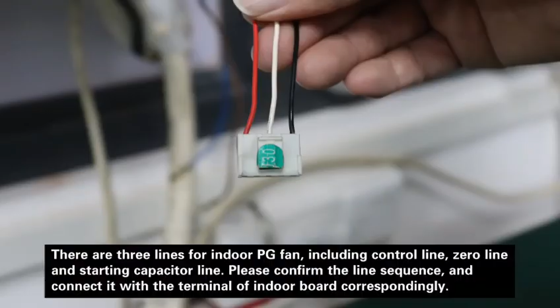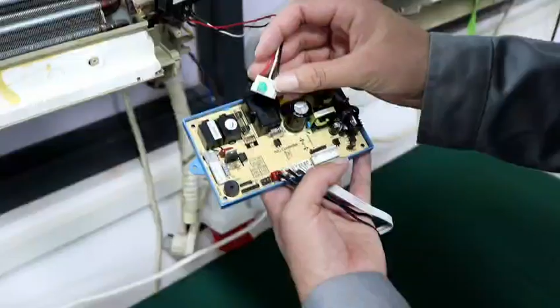Secondly, is the installation of indoor PG fan. There are 3 lines for indoor PG fan, including control line, zero line, and starting capacitor line. Please confirm the line sequence and connect it with the terminal of indoor board correspondingly. Connect the indoor PG fan. Connect the starting capacitor.